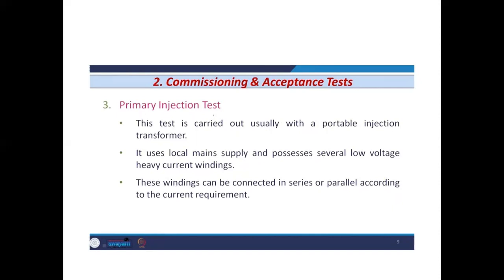It uses the local mains supply and possesses several low voltage heavy current windings. These windings can be connected in series or parallel according to the current requirement. So if we want to increase the current, we have to connect them in parallel, because in parallel the current is increased.